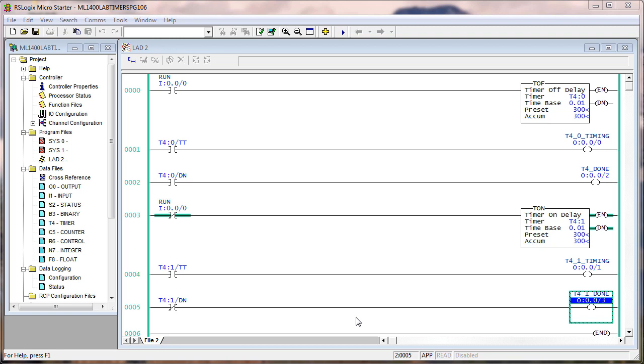Output 0 and 2 for T4 0, that's being addressed by a TOF. And then T4 1, it's a TON, but we flipped the, we inverted the input, so we're going off of the false starts it instead of true. Input 0 is off right now, but we use the true of off, which is true, and it ran the timer up to 300. If you look at the two timer instructions, or if you look at the control bits, you might get confused.